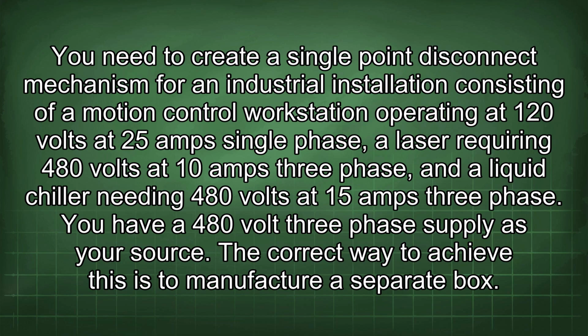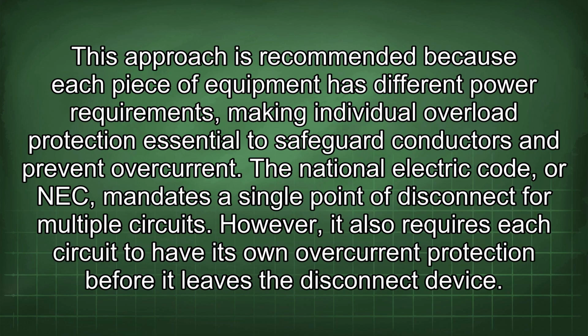The correct way to achieve this is to manufacture a separate box. This approach is recommended because each piece of equipment has different power requirements, making individual overload protection essential to safeguard conductors and prevent overcurrent. The National Electric Code, or NEC, mandates a single point of disconnect for multiple circuits. However, it also requires each circuit to have its own overcurrent protection before it leaves the disconnect device.